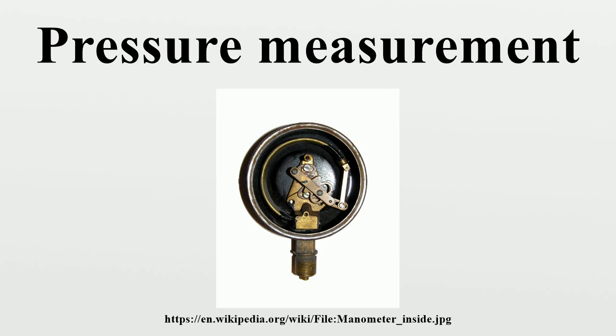Thus, a vented gauge reference pressure sensor should always read zero pressure when the process pressure connection is held open to the air. A sealed gauge reference is very similar, except that atmospheric pressure is sealed on the negative side of the diaphragm. This is usually adopted on high-pressure ranges such as hydraulics, where atmospheric pressure changes will have a negligible effect on the accuracy of the reading, so venting is not necessary. This also allows some manufacturers to provide secondary pressure containment as an extra precaution for pressure equipment safety if the burst pressure of the primary pressure sensing diaphragm is exceeded.